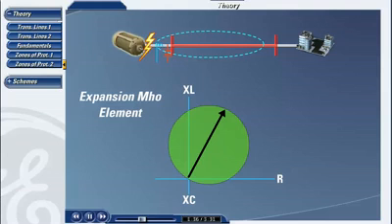On faults that occur very close to the point where the currents and voltages are being measured, some relays may have difficulty distinguishing whether the fault is inside or outside their zone of protection. To overcome this difficulty, the relay can change the size of the MHO circle when the calculated impedance is very near the origin. This is sometimes referred to as an expansion MHO element.